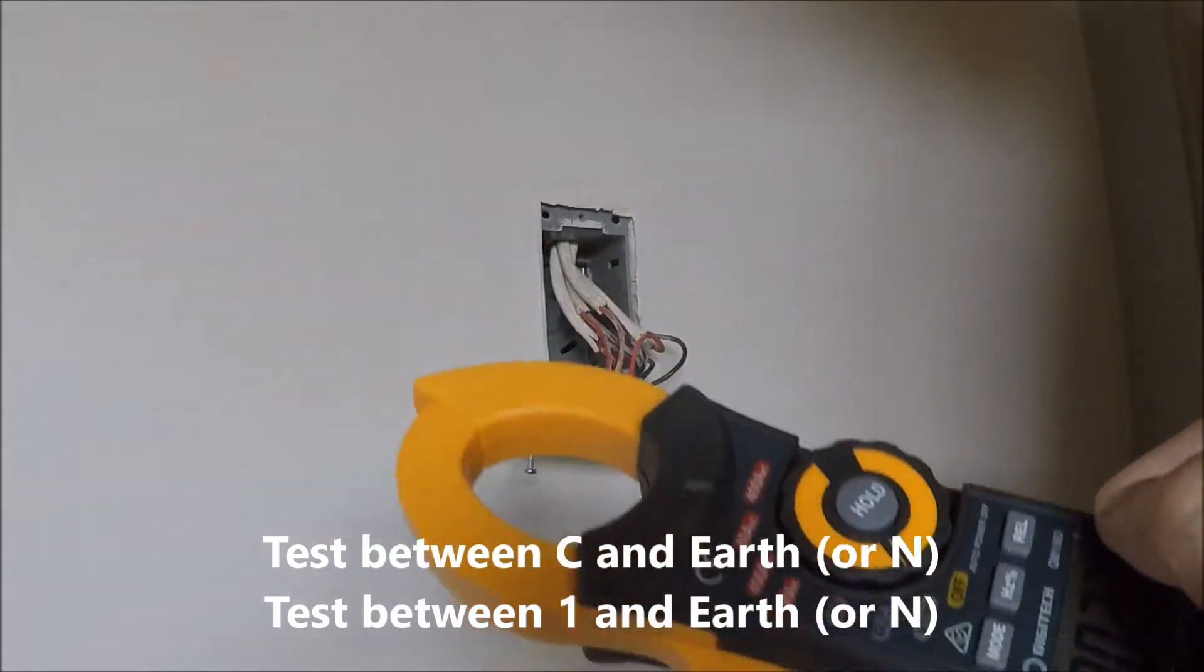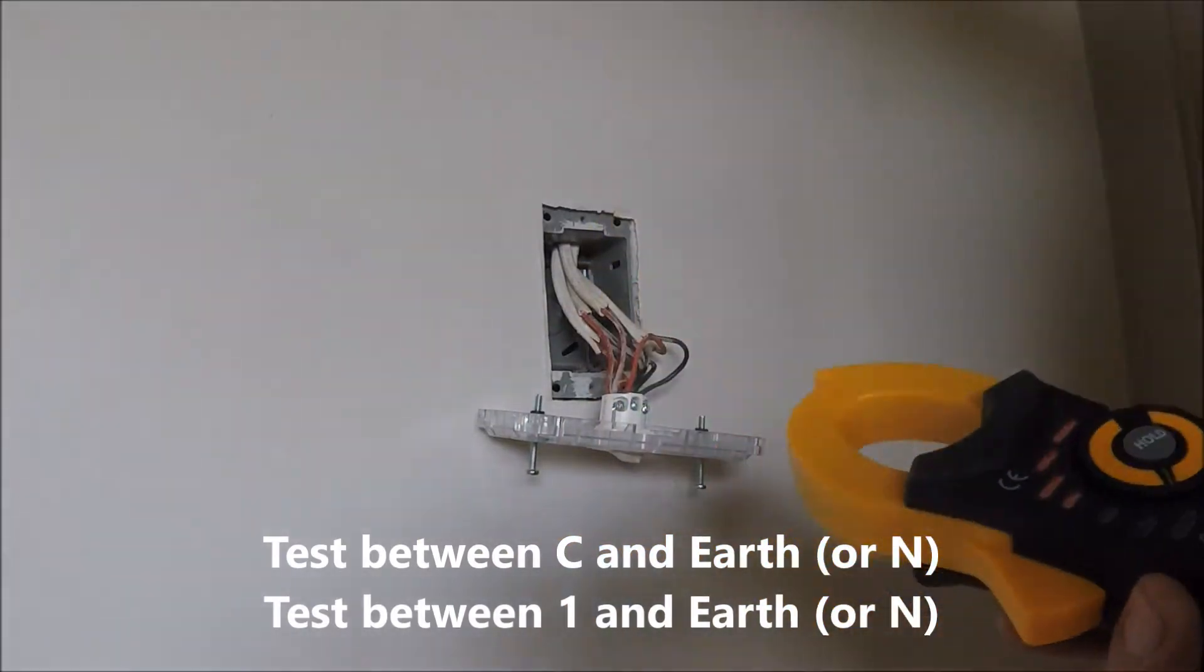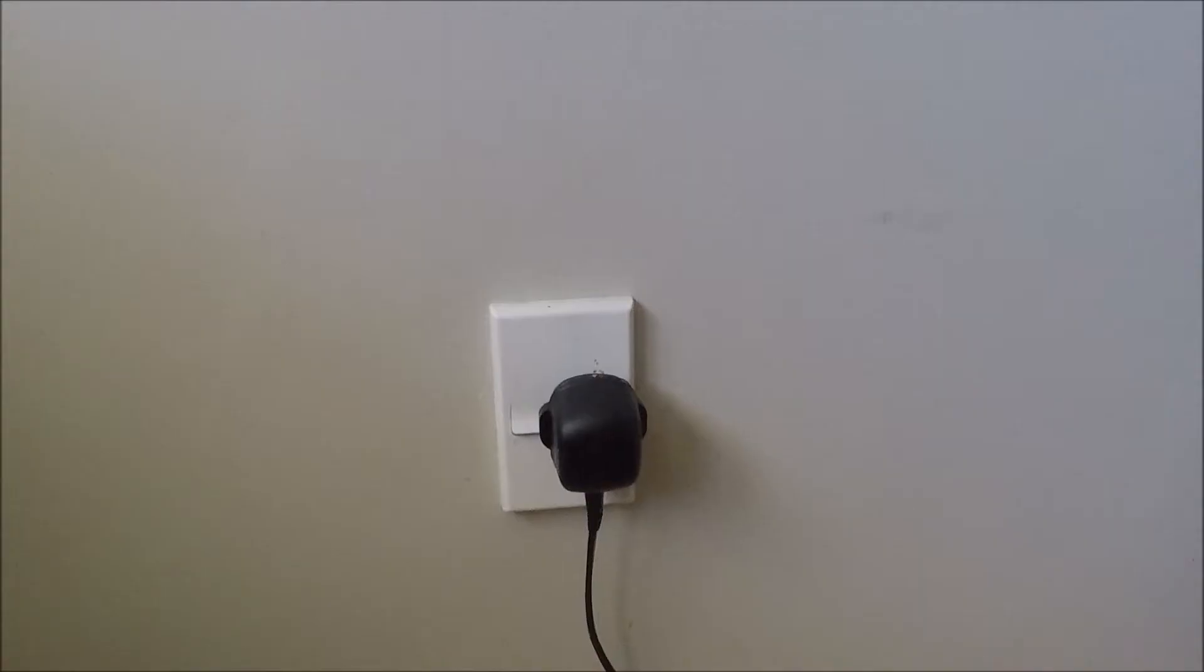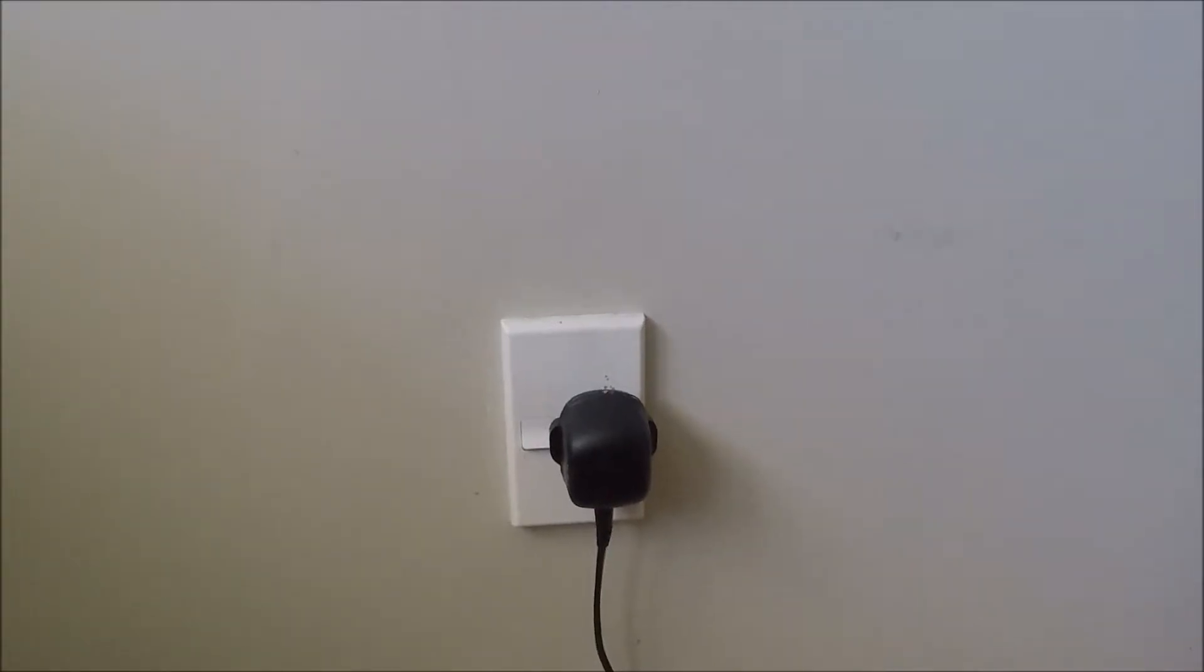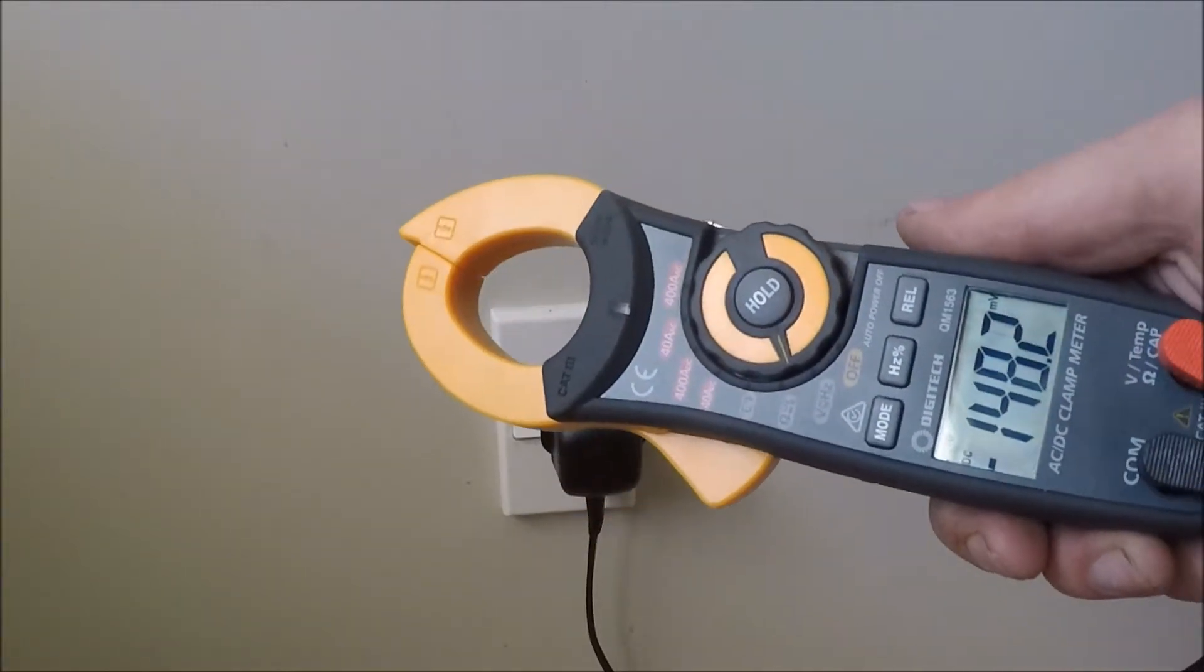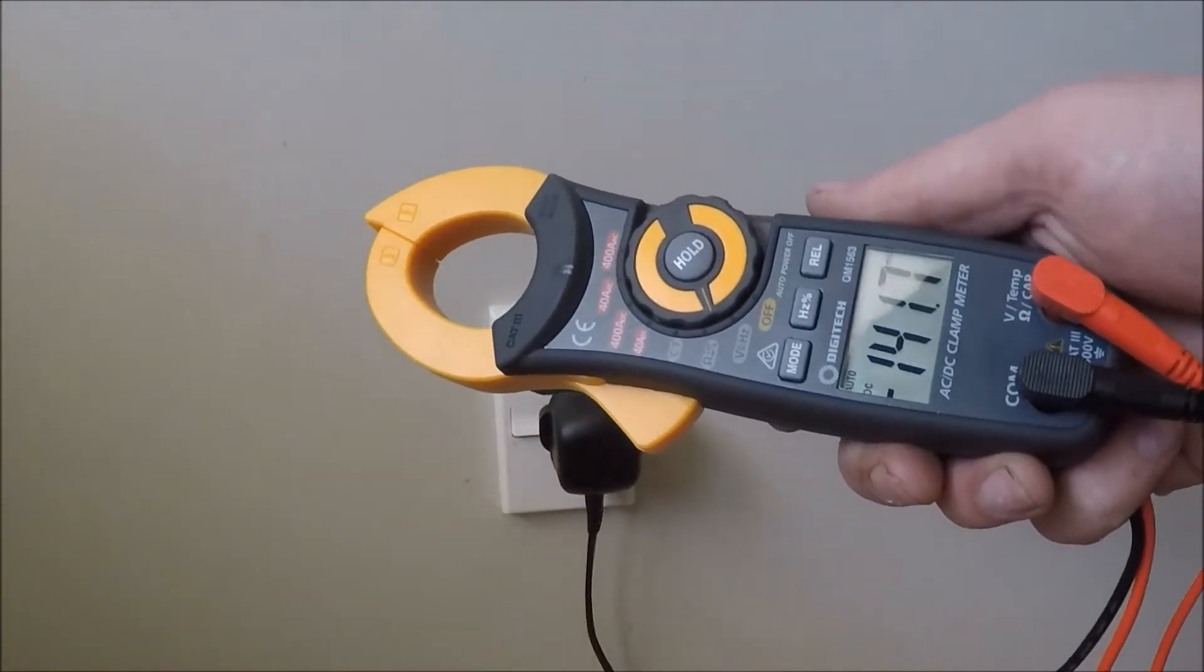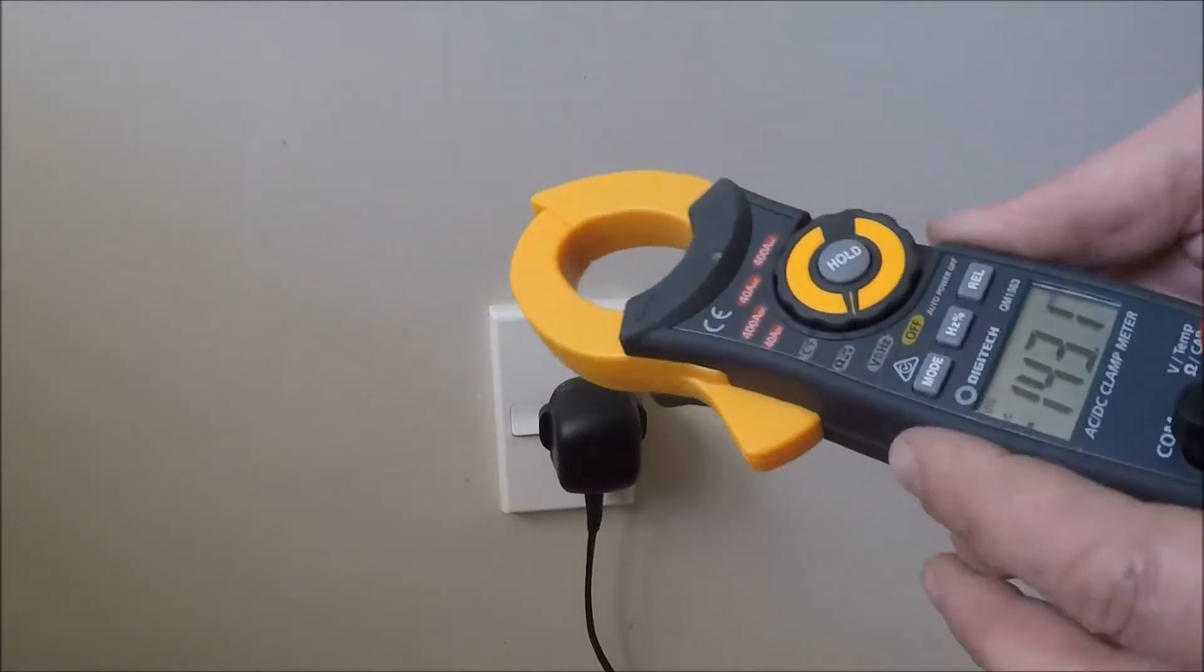Now what you want to do is prove that your meter works. So what we've just done is we've proved that the circuit's dead. But now what we need to do is test that this meter is functioning correctly.